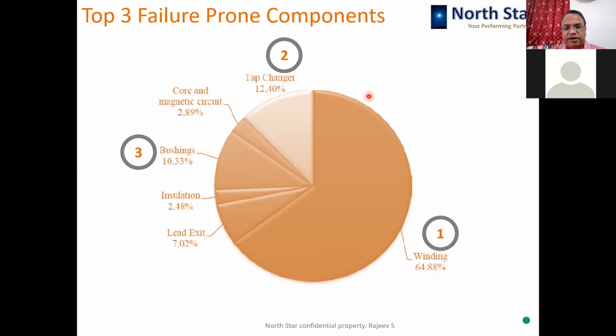So it is being deliberated, and it is almost decided that for the transformers in the transmission network up to 220 kV, probably OLTCs will be removed, or for the transformers which are in service, the OLTCs will not be used as such. Several operations of the OLTCs cause different types of problems, different transients and other issues, and because of that, transformer failures have been found increasing. So that is one thing.